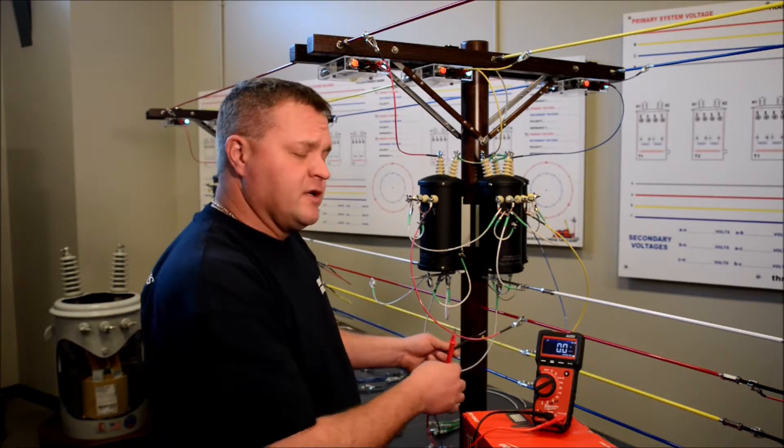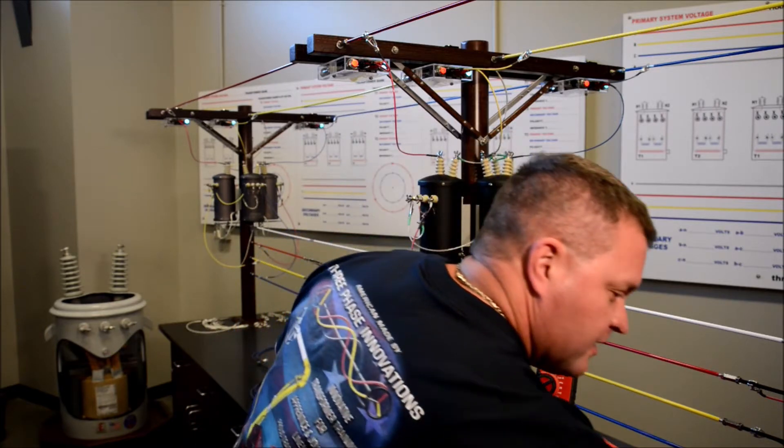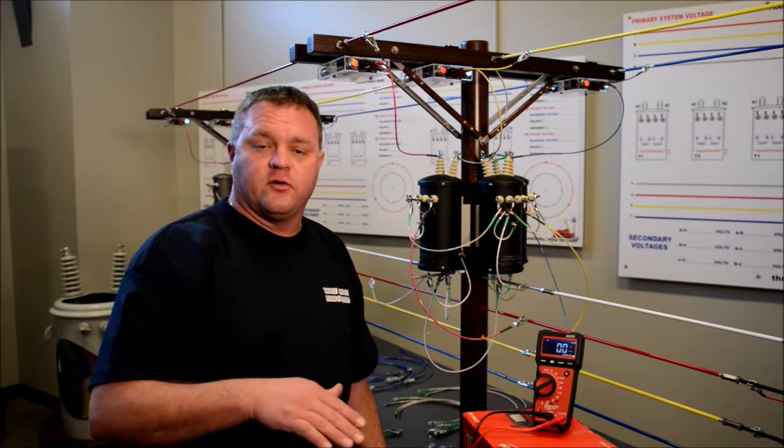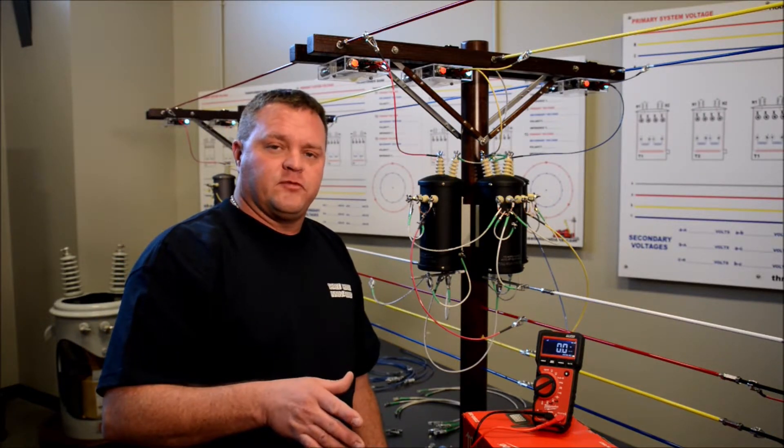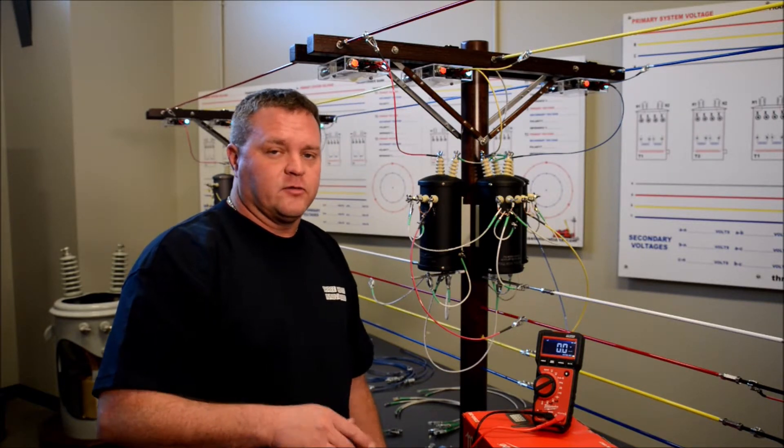Come over here and check voltage. Now when we've done the test, the voltage increases. Now what do I have here? Approximately 17 percent phase to ground from A, B, and C to ground is about 17 percent increase. Phase to phase, approximately a 5 percent increase.